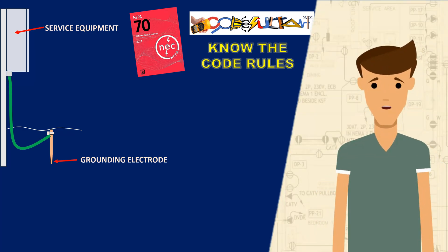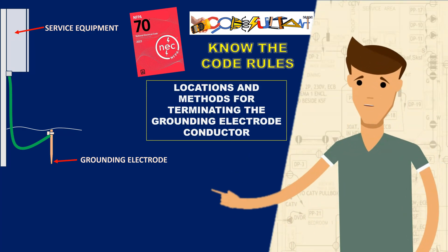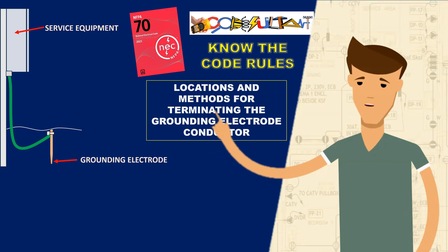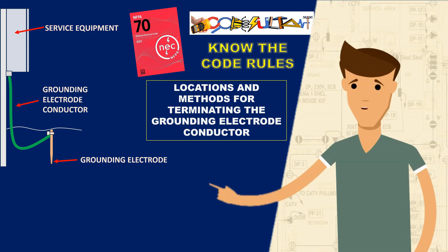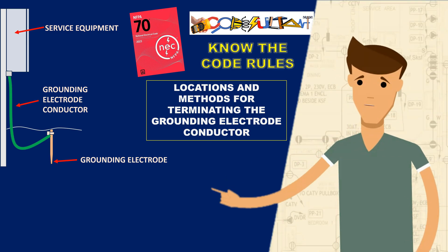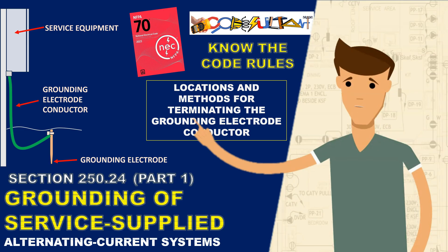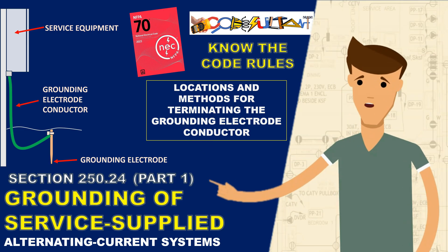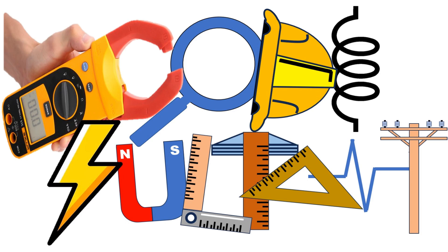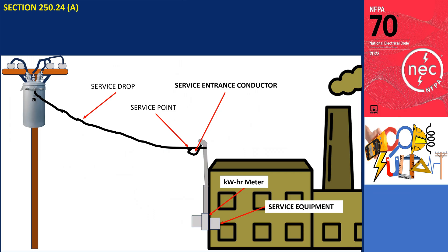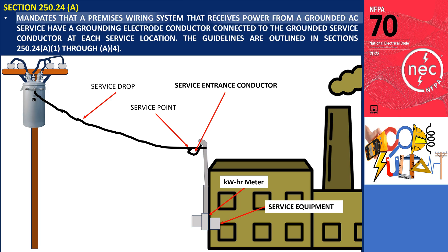During our discussion, we will explore the prescribed guidelines and techniques for connecting the grounding electrode conductor in cases where the premises wiring is supplied from a grounded system. These regulations can be found in Section 250.24 of the code, which pertains to grounding service-supplied alternating current systems. Hello everyone, welcome to the Codesultant channel. Section 250.24(a) mandates that a premises wiring system receiving power from a grounded AC service have a grounding electrode conductor connected to the grounded service conductor at each service location.